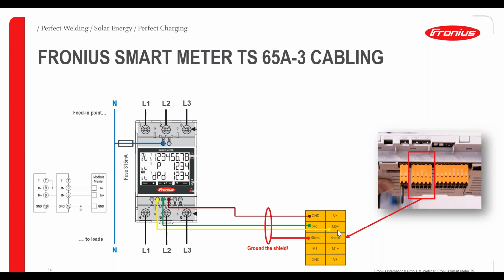The connection itself to the data communication card, it's simple. It's like our old Snap inverters. So that's just data minus, data plus, and the ground. Just the naming which is different. It's M0 minus, M0 plus, and the ground, but that's the same naming as it was in the Snap inverters. That's the same positioning. So we go from the pin number 8 to the data plus, from the pin number 9 to data minus, and we go from pin number 10 to the ground. And after that, we use a shielded cable here for data plus, data minus, and the ground, and we ground the shield in this specified pin here.